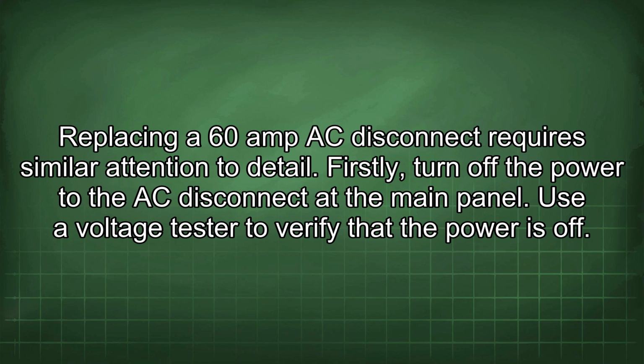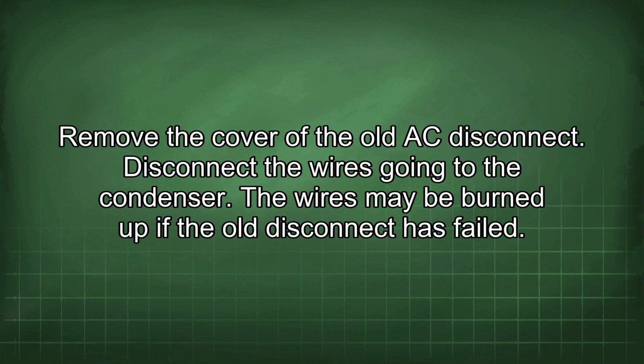Replacing a 60 amp AC disconnect requires similar attention to detail. Firstly, turn off the power to the AC disconnect at the main panel. Use a voltage tester to verify that the power is off. Remove the cover of the old AC disconnect. Disconnect the wires going to the condenser. The wires may be burned up if the old disconnect has failed.